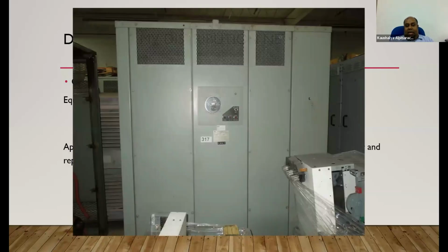Yes, this is another transformer obstructed with some spare parts, maybe switchgear. And to the right side of the transformer, you have some LV cabinets, and you see some handles there. That means those are removable, but that is locked with nuts and bolts. So the person who is removing should have adequate space to remove those nuts and bolts. And if there is any chance of replacing the particular transformer, we'll have to do some more changes.